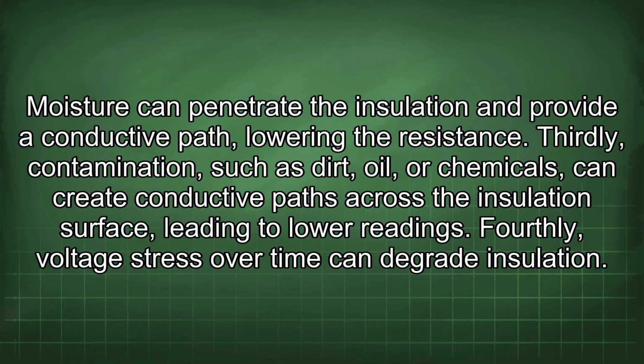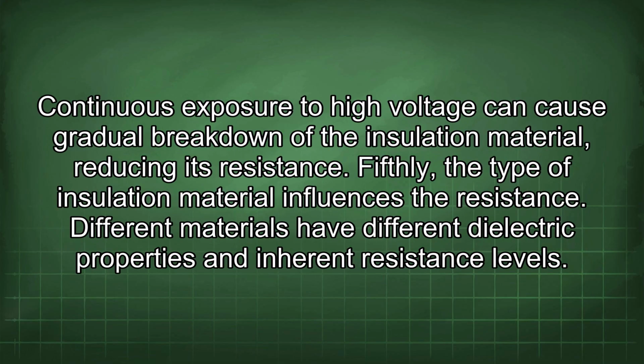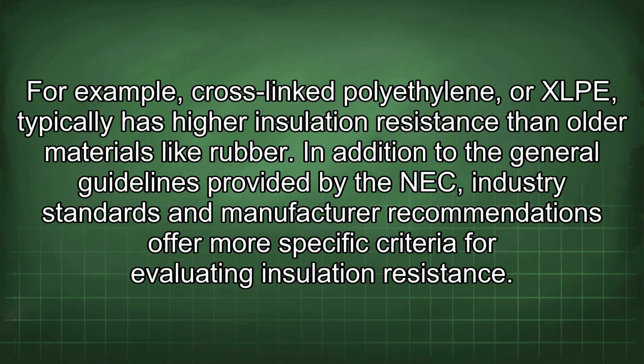Fourthly, voltage stress over time can degrade insulation. Continuous exposure to high voltage can cause gradual breakdown of the insulation material, reducing its resistance. Fifthly, the type of insulation material influences the resistance. Different materials have different dielectric properties and inherent resistance levels. For example, cross-linked polyethylene, or XLPE, typically has higher insulation resistance than older materials like rubber.